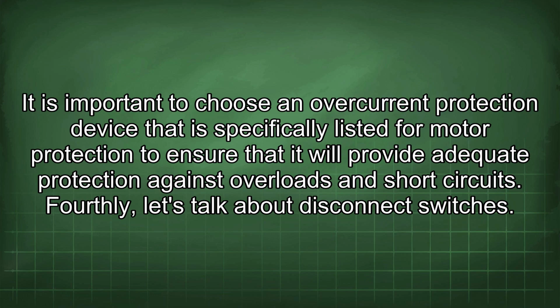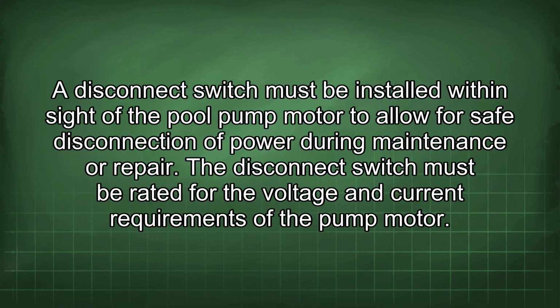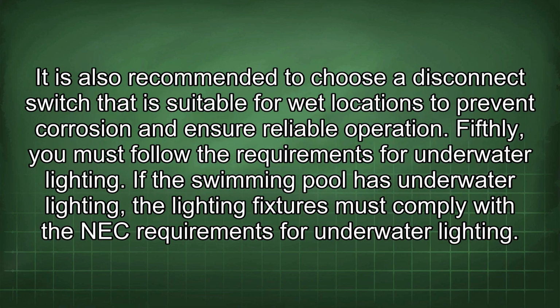Fourthly, let's talk about disconnect switches. A disconnect switch must be installed within sight of the pool pump motor to allow for safe disconnection of power during maintenance or repair. The disconnect switch must be rated for the voltage and current requirements of the pump motor. It is also recommended to choose a disconnect switch that is suitable for wet locations to prevent corrosion and ensure reliable operation.